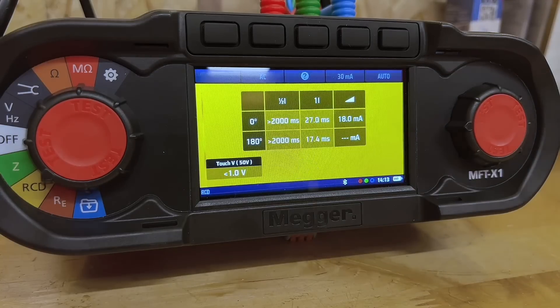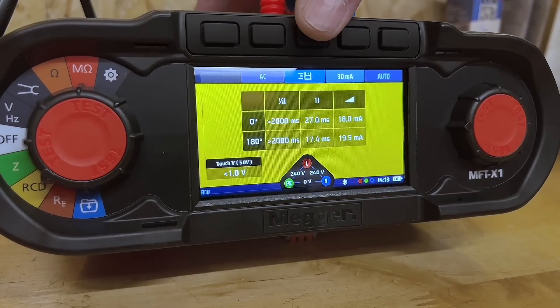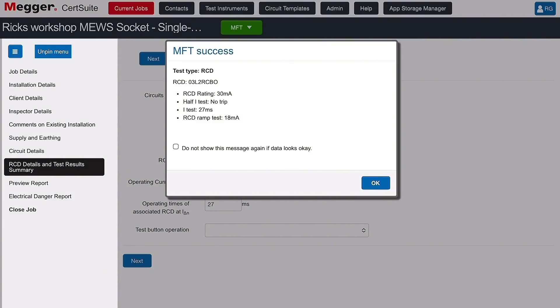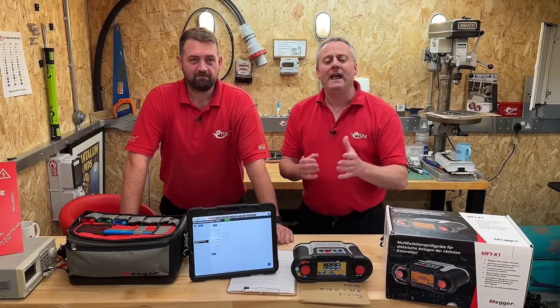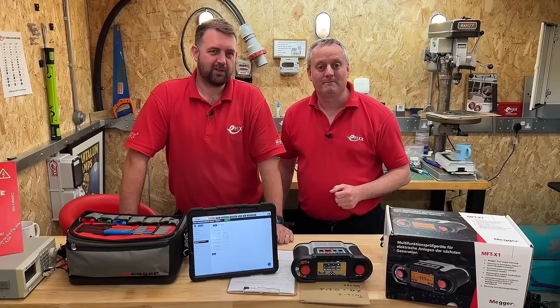With the RCD test completed, we need to get those results onto the iPad. Press the save button, tell it it's on L1, and transfer the results. On screen it gives us the results — press OK and it has populated the operating times for us. We had 27 and 17.4 milliseconds and it's chosen the maximum of the two — it's done that for you automatically. I truly am an analogue man trapped in a digital world, but thanks to the Megger MFT-X1 tester, the cert suite software and Rick's tutelage, even I got there. If you're wondering what's inside the bag for the X1 tester, check out the short video on screen.